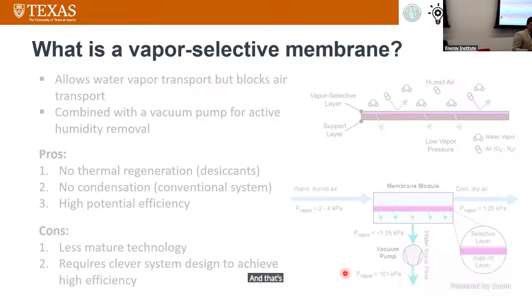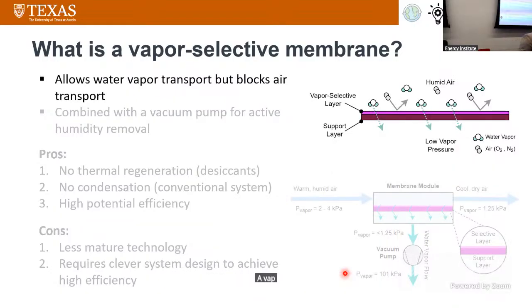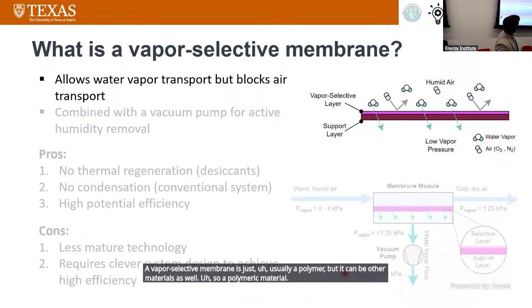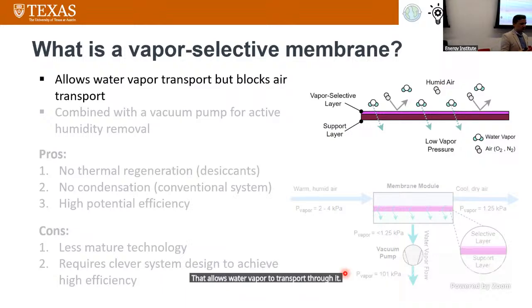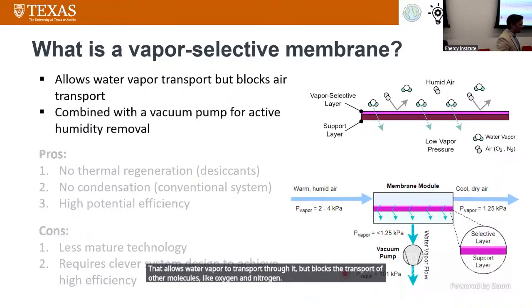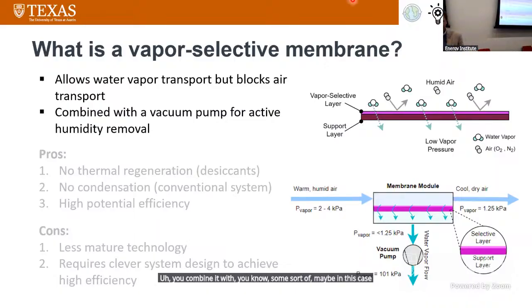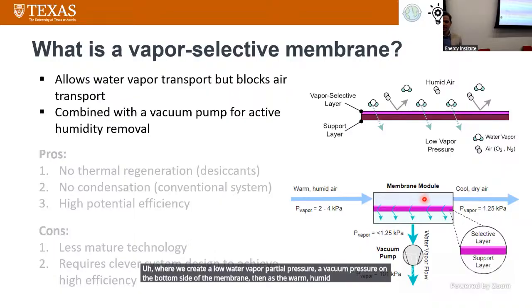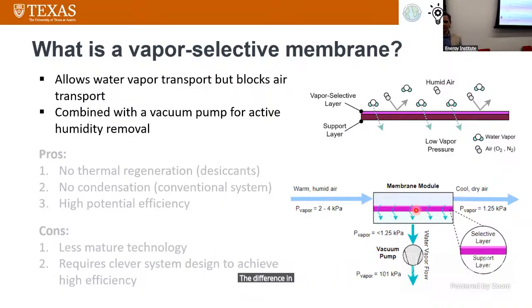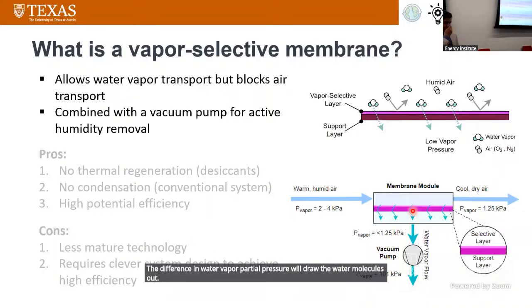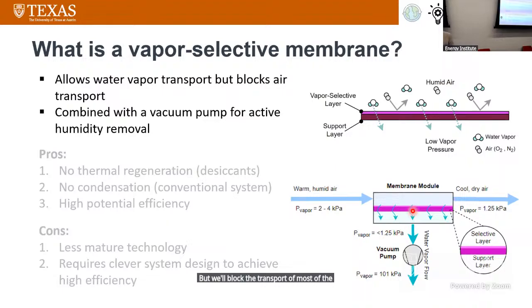That's where water vapor selective membranes come in. A vapor selective membrane is usually a polymer, though it can be other materials, that allows water vapor to transport through it but blocks the transport of other molecules like oxygen and nitrogen. You combine it with something like a vacuum pump, creating a low water vapor partial pressure or vacuum on the bottom side of the membrane. As the warm humid air flows over the membrane, the difference in water vapor partial pressure draws the water molecules out while blocking most other molecules. Some air still gets through, but far more water vapor passes than air molecules.